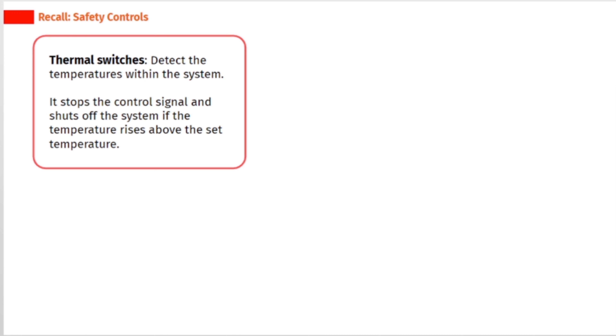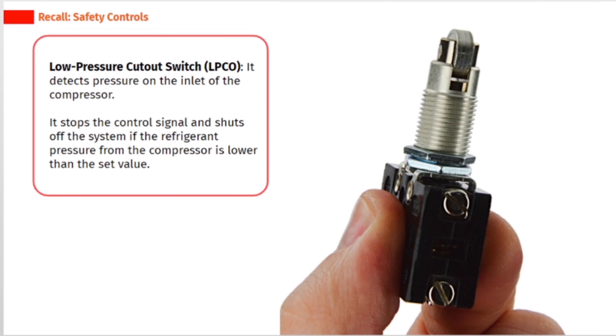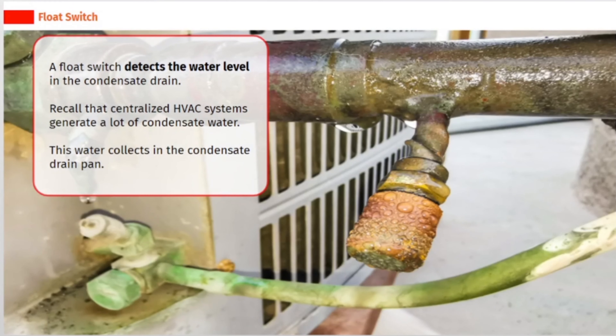Thermal switches stop the control signal and shut off the system if the temperature rises above the set temperature. The high pressure cut out switch (HPCO) detects pressure on the outlet of the compressor and shuts off the system if the refrigerant pressure is higher than the set value. The low pressure cut out switch (LPCO) detects pressure on the inlet of the compressor and shuts off the system if the refrigerant pressure is lower than the set value.